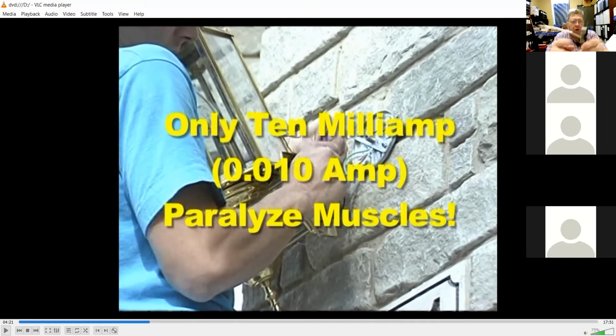So when you have missing current in a hair dryer or a hand drill or whatever it is, here's what can happen. The missing current could possibly end up getting in your body and going to ground through you. And here's what happens. The ground fault circuit interrupter, if it sees a difference of around 4 to 6 milliamps of current between these, to where you're missing around 4 to 6 milliamps coming back, it trips on the inside. Then it trips like a breaker does. It has a trip mechanism built into this thing.